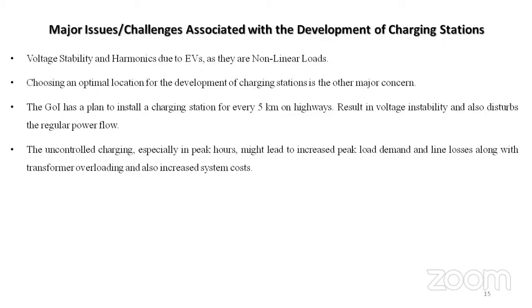Suppose I have an electric vehicle charging station somewhere near a junction. At around 9:30 or 10 o'clock, all the shops will be on and there will be a sudden rise in the load demand. At the same time, if I charge 4 or 5 electric vehicles together, that will further increase the peak load demand and the transformer will be overloaded, resulting in tripping of the circuit or the transformer.